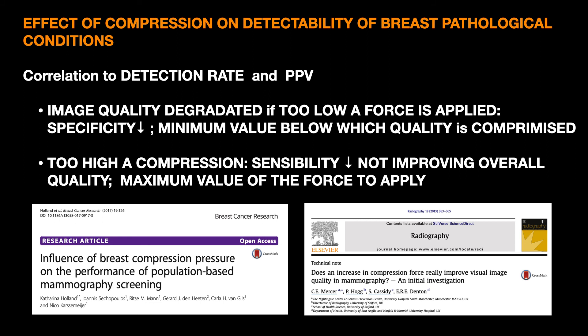We do know that image quality is degraded if too low a force is applied, with a decrease in specificity. It has to be a minimum value below which the quality of the image is compromised, and it should be based on scientific evidence. Furthermore, there are many researchers who suggest that too high a compression force may reduce sensitivity. It is reasoned that softer tumours may become less conspicuous. Pathological tissue may spread out so that the contrast to healthy tissue drops. Other studies show that anyway after a certain value, a further level of compression force does not improve the overall image quality.